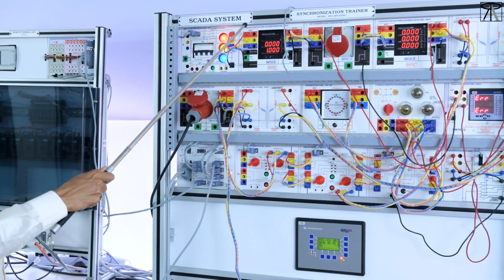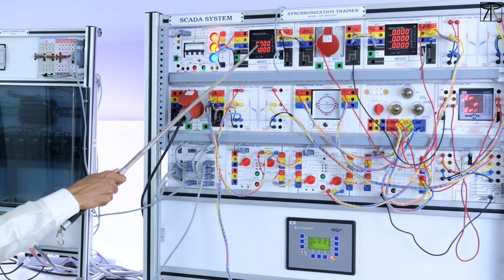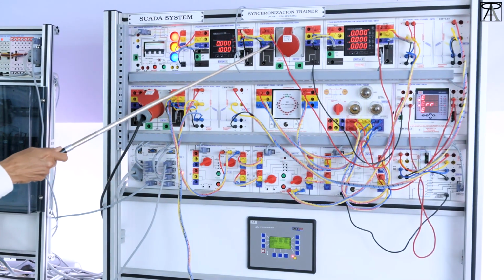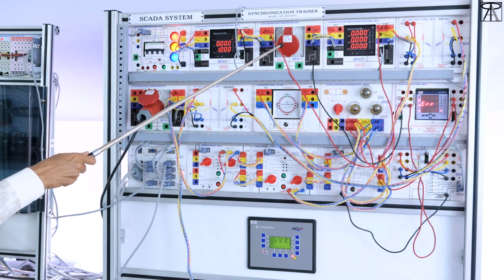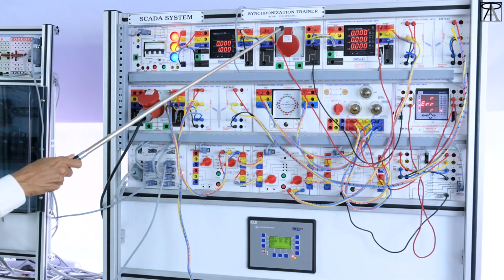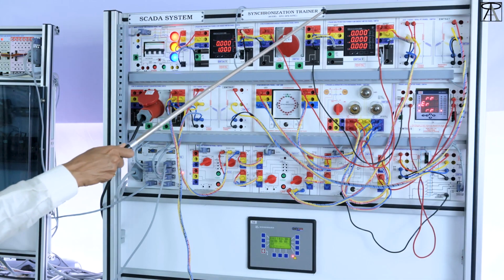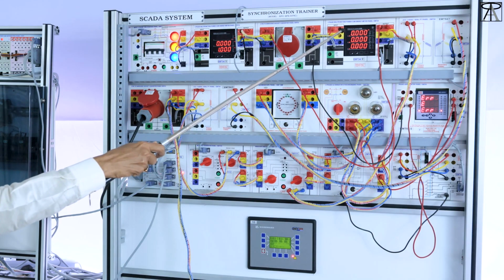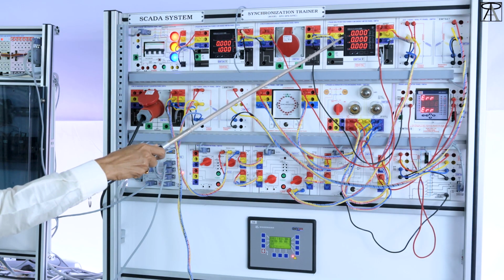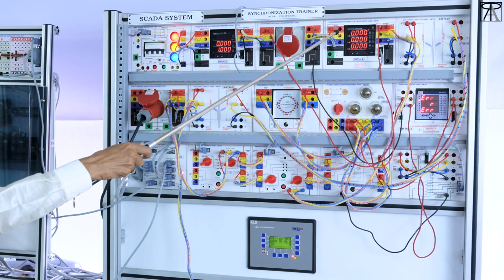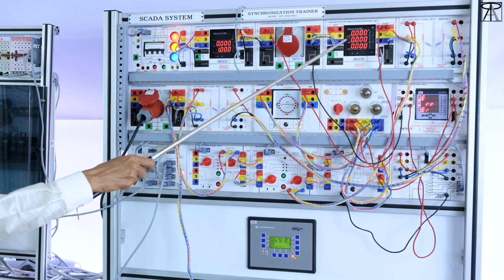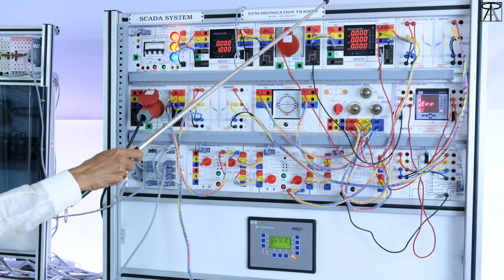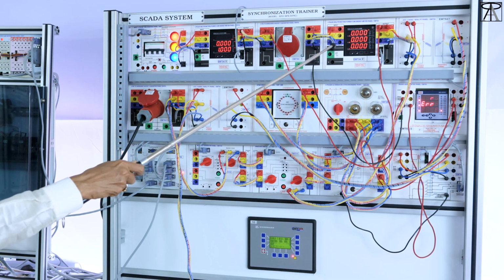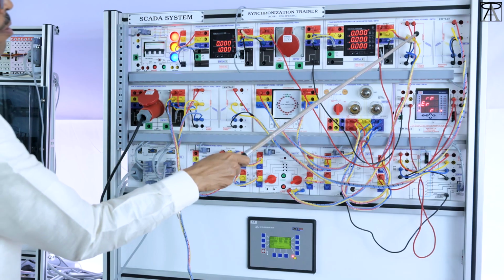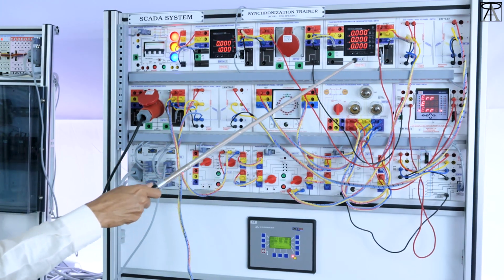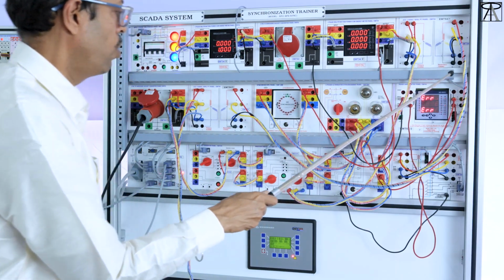And this is the grid power supply measurement panel, a multifunction power meter panel. And this is an extension box for the grid power supply for future use, for 3-bus flow and 4-bus flow study purposes. This is the same measurement panel, a multifunction power and energy meter panel. We have used Rishabh multifunction meters, which are MODBUS based, so we can use them with computer interface as well as SCADA. This is the PT panel, 415 volt primary and 110 volt secondary for the synchronization relay.